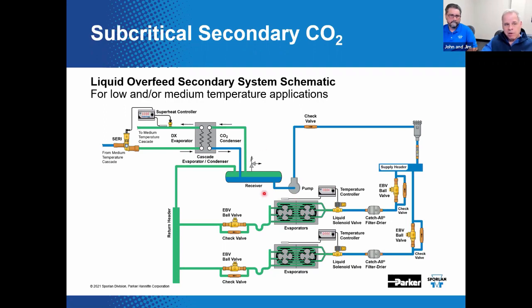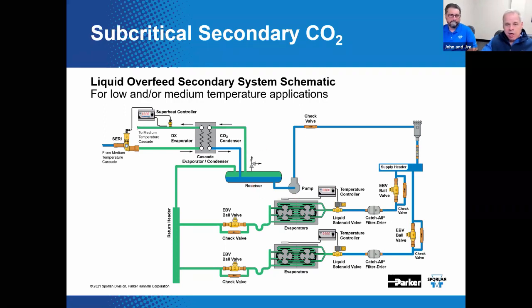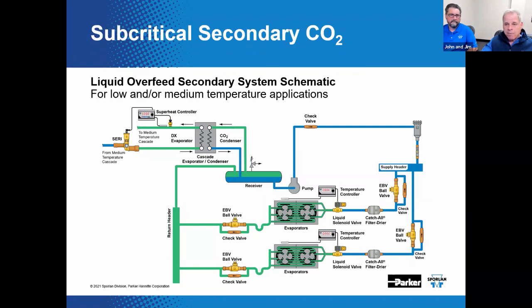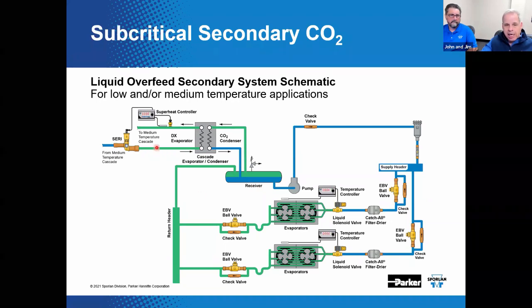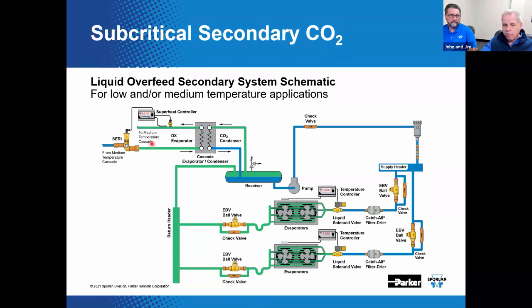So there's the pump, there's a receiver. And if we start at the upper left side of the schematic, you can see piping with an electrically actuated, electronically controlled expansion valve that controls the superheat of the HFC refrigerant leaving the cascade evaporator condenser. The liquid receiver is also called a liquid vapor separator, since it is designed to ensure only liquid is introduced to the pump to prevent cavitation. So there's that receiver, here's the pump. You only want the pump to have liquid, and you only want the compressor to have vapor. So it's a good idea.